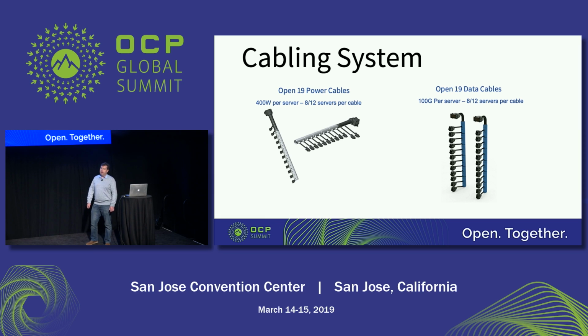These are the cables we use to connect the bricks to the power shelf and to the network switch. It's 400 watts per server connection, with either 8 or 12 servers per cable based on enclosure size. So if you deploy a wide brick, you can use 2 of those power connectors, bringing total power per brick up to 800 watts. And if you use a full 2U, that's 4x that. So you're not limited to just 1 power connector per brick.